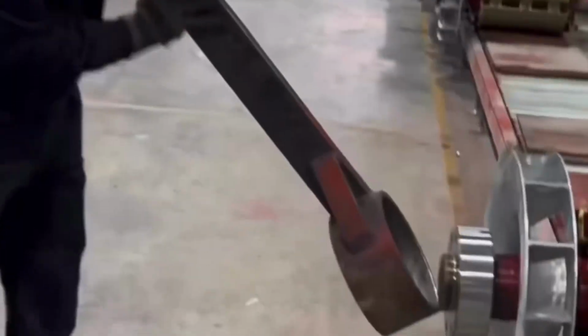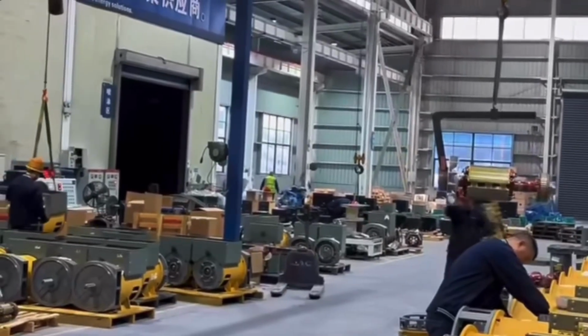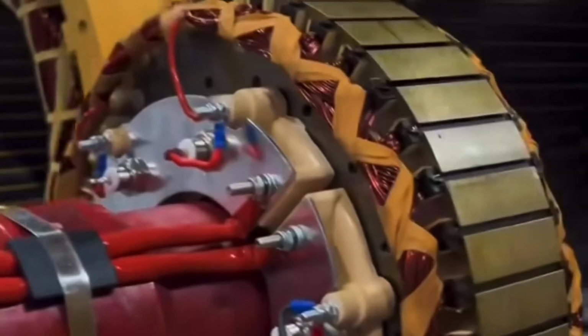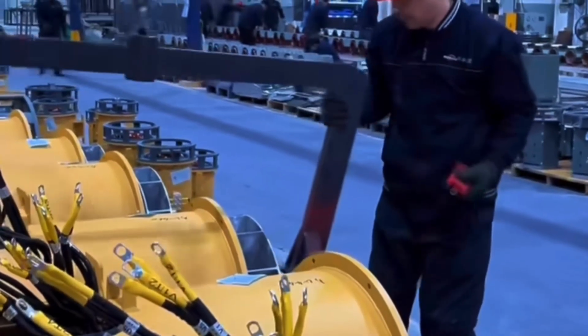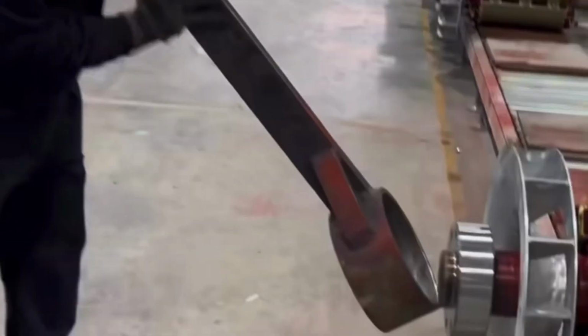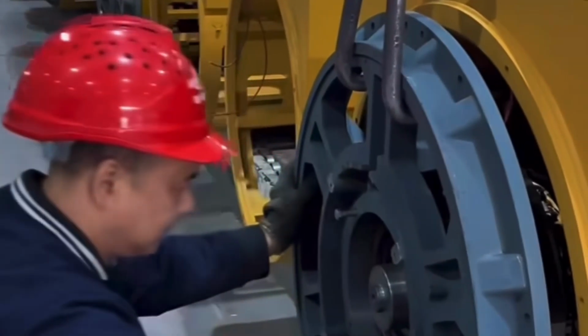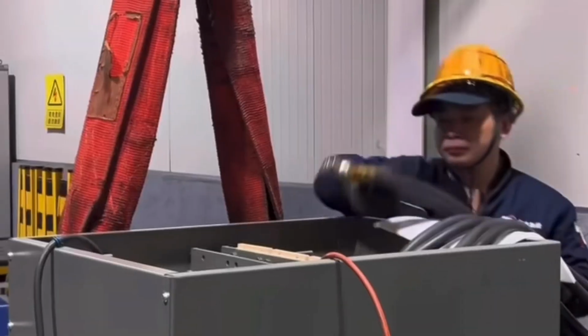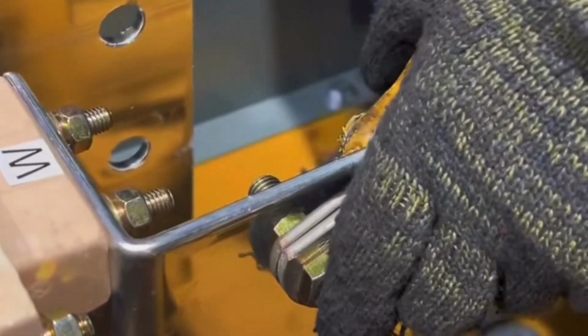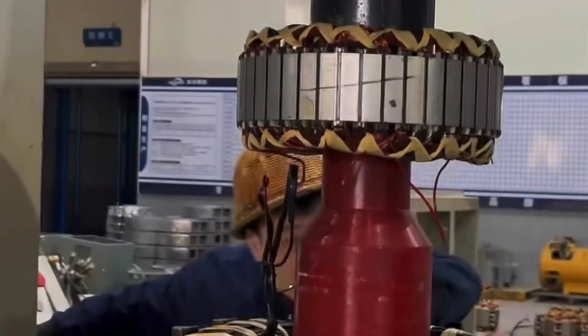With all major components prepared, the process moves into one of the most critical stages, final assembly of the alternator. It begins with the careful installation of the rotor into the stator housing. Using heavy lifting equipment and precision alignment tools, engineers ensure that the rotor is perfectly centered. Even the smallest misalignment can lead to vibration, efficiency loss, or long-term damage. Once positioned, the rotor is securely mounted onto the shaft, forming the rotating core of the alternator.